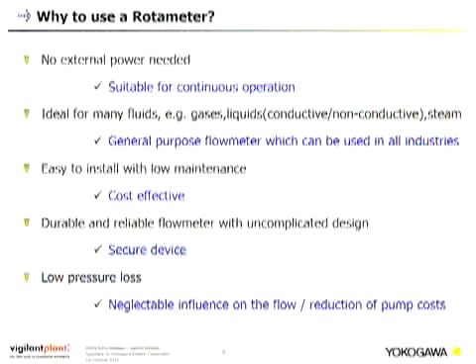Why use a Rotameter? No external power is needed — you just need the flow, making it suitable for continuous operation. It is ideal for many fluids including gases, liquids, conductive and non-conductive media, and steam, making it a general purpose flow meter for all industries. It is easy to install with low maintenance, making it very cost effective. It is durable and reliable with uncomplicated design — just a conical tube and a float. The fewer parts you have, the fewer parts can fail. It also has low pressure loss, reducing pump costs.